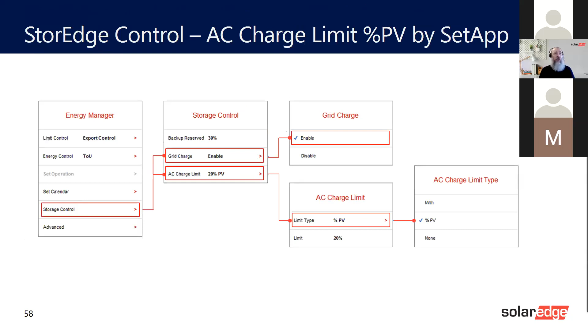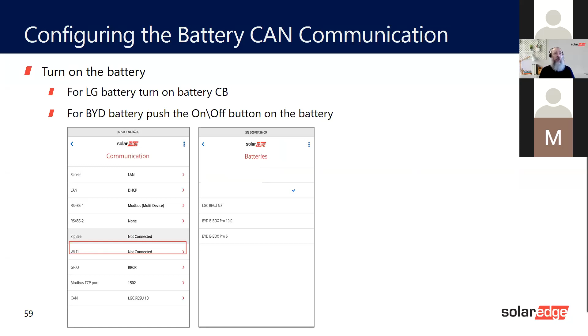Then do configuration. Turn on the LG battery circuit breaker, and make sure the BYD safety switch is set correctly. Then you can see on here what you can select - the battery status should all be showing.